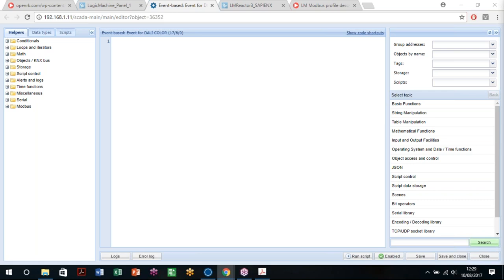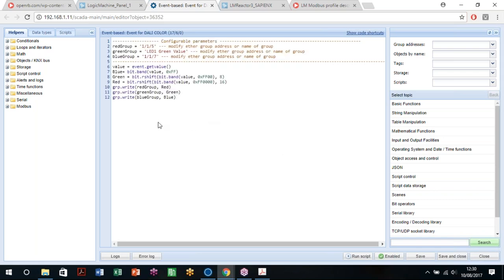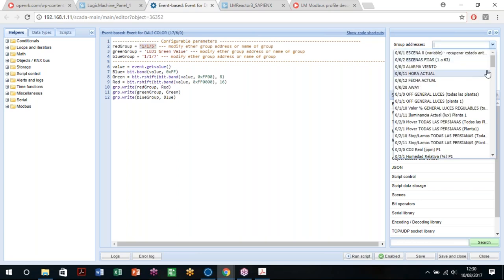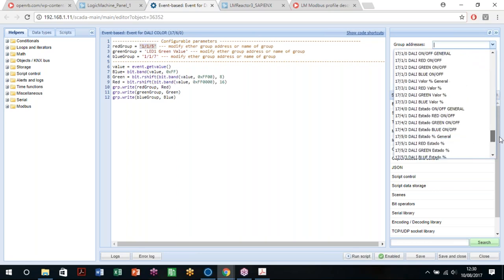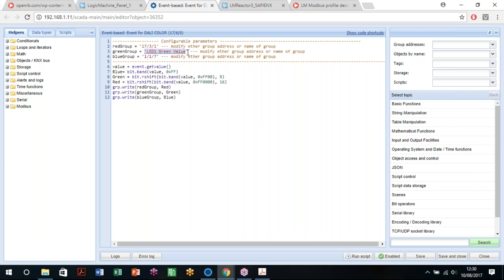So the code, how to split a 3-byte object into three objects of 1 byte. So we copy and paste the script. This is the script, and the only thing that we're going to change is the object addresses of each group. In this case, we will change it to 1731, which is the DALI red. We will change the green value to the 1732 green value, and the blue value, we're going to set it to 1733. Blue value. So the rest of the code, we should not touch it. It does what it's meant to do.